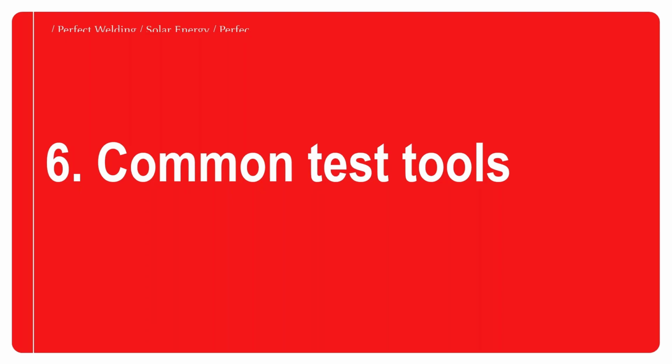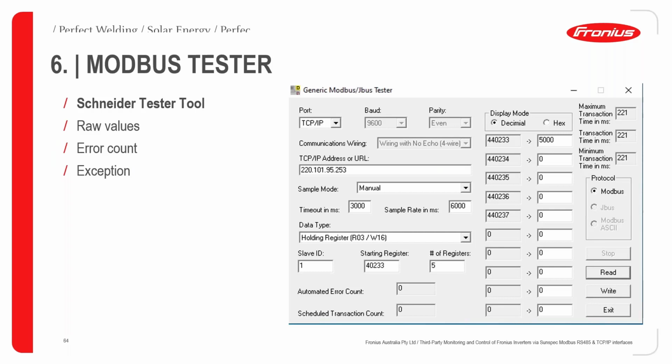So, common test tools. This is a very important bit, because using the same tools all over is important. Every application is different. We're not going to go over every possible tool, but we will go over 2 tools that are free for you to use and deploy. The first one is the Schneider tester tool. Why this tool? Maybe because Schneider did invent Modbus quite a bit, and this tool does offer some unique capabilities. It's pretty simple. It's a run-on tool. You can pull up to 10 registers, unfortunately. You can write as well.